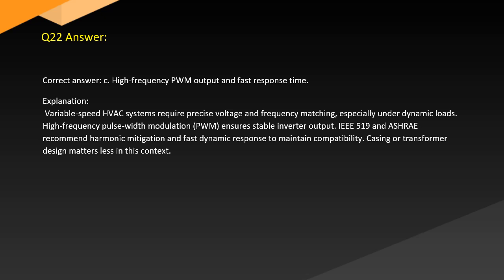Answer. Correct answer: C. High frequency output and fast response time. Explanation. Variable speed HVAC systems require precise voltage and frequency matching, especially under dynamic loads. High frequency pulse width modulation, PWM, ensures stable inverter output. IEEE 519 and ASHRAE recommend harmonic mitigation and fast dynamic response to maintain compatibility. Casing or transformer design matters less in this context.